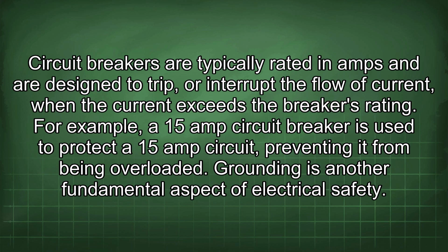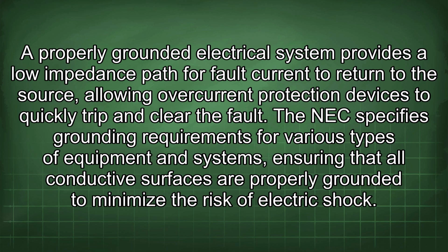Grounding is another fundamental aspect of electrical safety. A properly grounded electrical system provides a low impedance path for fault current to return to the source, allowing overcurrent protection devices to quickly trip and clear the fault. The NEC specifies grounding requirements for various types of equipment and systems, ensuring that all conductive surfaces are properly grounded to minimize the risk of electric shock.